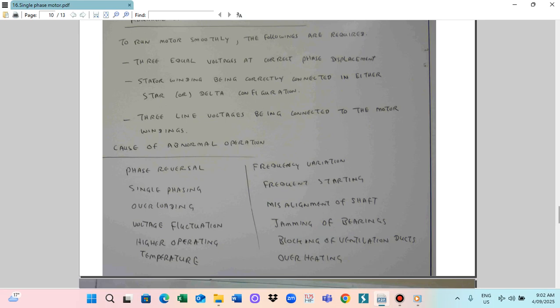So how can you determine overload and short circuit? Okay, give me the answer. When you see the motor, you can see. So how can you identify the short circuit and overload? Both trip the circuit, but with a three-way circuit breaker you cannot properly identify which, because once it trips, everything trips together. But if you use a fuse system, this is for the motor as a fuse.